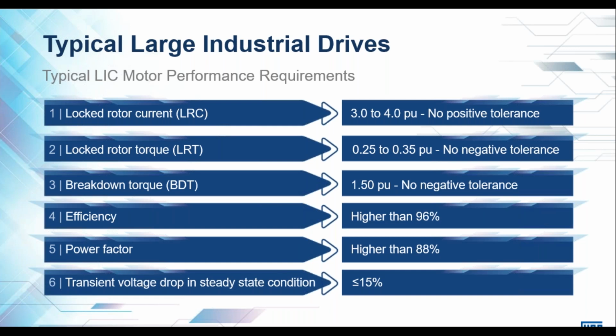So some constraints or considerations that we need to take into account when designing a low inrush current motor. These are the design considerations that we aim for. So in general, what we're aiming to achieve is a locked rotor current of 3 to 4 times the nominal rating, and a locked rotor torque of at least between 0.25 and 0.35 per unit of nominal. Our breakdown torque needs to remain at least at 1.5 per unit or greater.